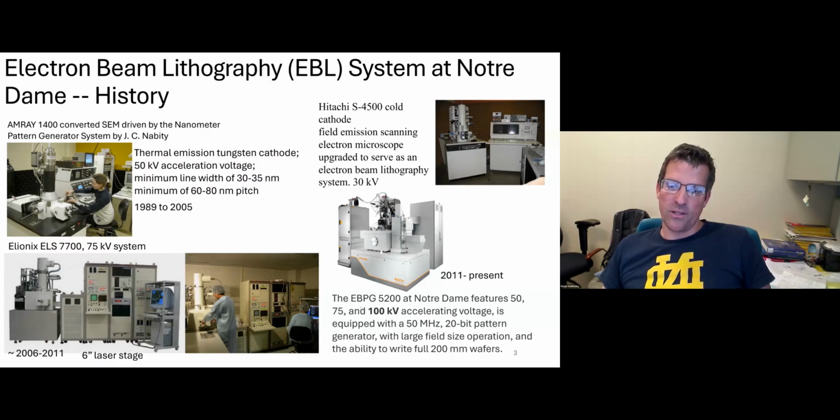You will make a lot of other users fall behind on their work, because it's not just a simple change like beam current. It actually takes a lot of work from the lab staff to change the acceleration voltages and to stabilize the system. So pretty much exclusively, everybody uses this system at 100 kilovolt.